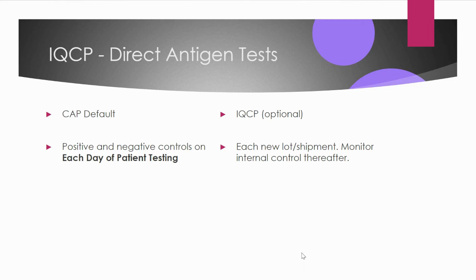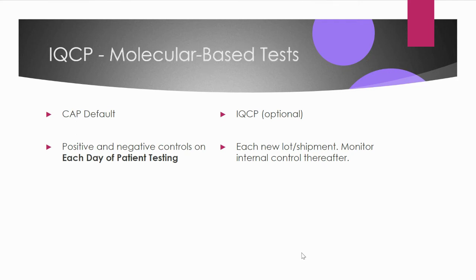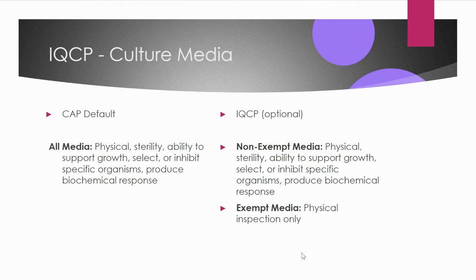If an IQCP is implemented — which is optional but saves money and staff effort — QC for direct antigen tests can be restricted to each new lot or shipment only, after which you just monitor the internal control. Similarly, for molecular-based tests like PCRs, CAP default requires positive and negative controls on each day of testing, while after implementing IQCP, QC is only required when receiving a new lot or shipment. For culture media, CAP default requires physical inspection, sterility, ability to support growth, select or inhibit specific organisms, and produce the intended biochemical response.